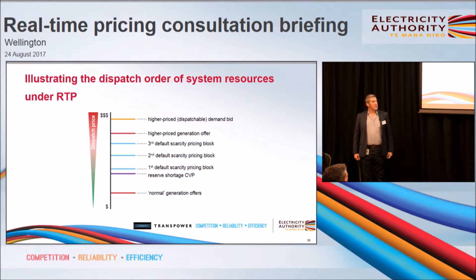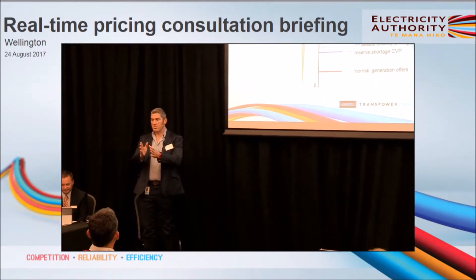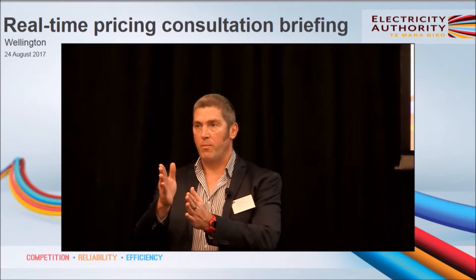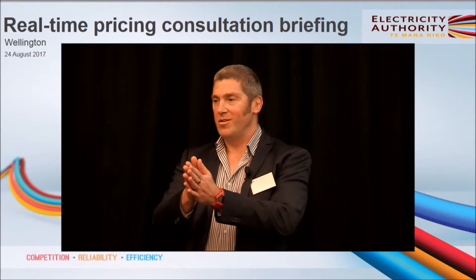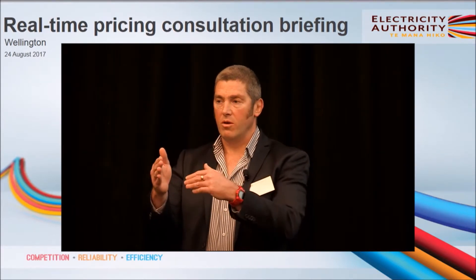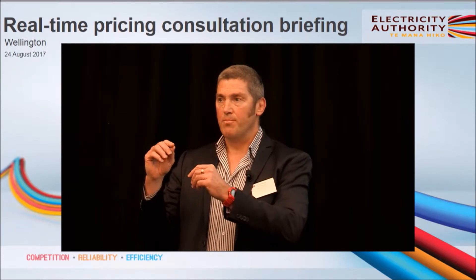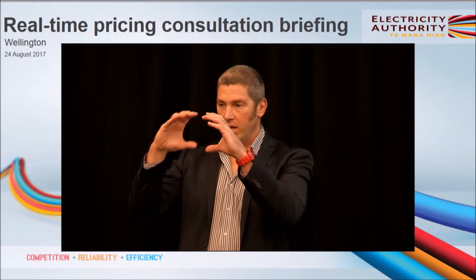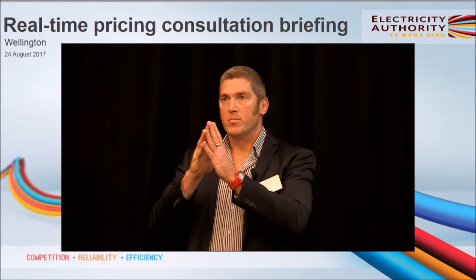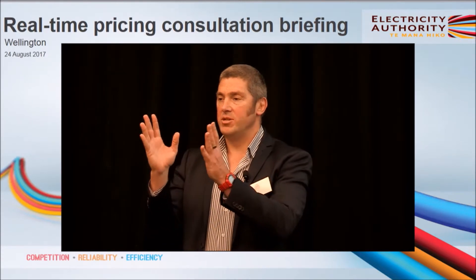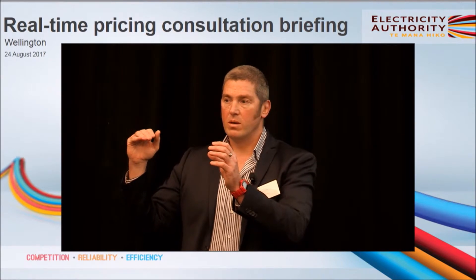This would be under a formal notice — seeking increased offers or seeking other resources to be made available. On a dispatch solution by dispatch solution basis, they're each just the one schedule. So if by the time you ran the next one conditions have changed — for example if load natively disappeared — then you might find that the next five-minute solution comes back onto the offers stack and can balance everything perfectly. In terms of how the optimiser SPD — scheduling, pricing, and dispatch — works, it's always got the reserve stacks, the energy stacks, and it knows the demand. Every time it runs, it's optimising the lowest cost solution between those. There's no ring-fencing of a generation offer when it's been used for reserve or vice versa — it's just what's the cheapest combination that meets all of the requirements.